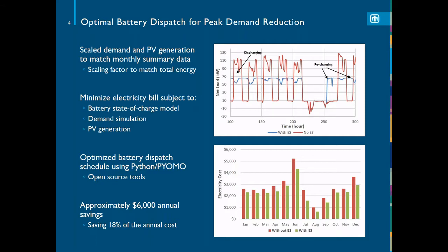All of this reduces the peak demand that the school requires, which is a pretty big benefit to their monthly bill. You can reduce it by about 50% most months, amounting to about $6,000 of annual savings, which is a significant chunk of what their bill was, about 10 to 20% on average, around 18%. Depending on the month, you get a particularly large benefit during high demand months, like summer months while students are still there, such as June.